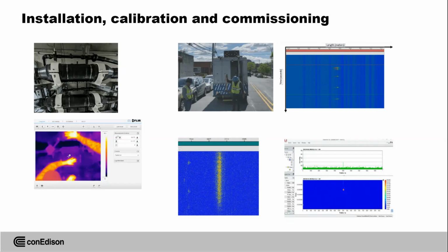So basically, that's what we installed. We installed and energized that system in 2019. We installed partial discharge monitoring, DTS monitoring, DAS monitoring for fault locating and construction activities. We install video and infrared vault inspection. We install video and infrared cameras. We install local vibration monitoring just to validate what we have from the fiber optic cable, because it's kind of diverted from the cable itself. That's why we install them on each cable, top, middle, and the bottom. We know vibration in the vaults is higher than vibration along the route because it's exposed to air and because we have hatches and it's in a heavy traffic area. We also install vault entrance alarm. So basically same fiber acting as a vault entrance alarm.